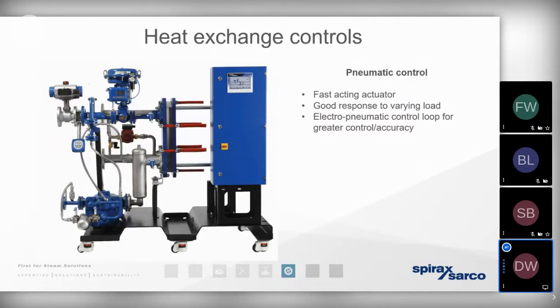So, for example, we can have a PLC panel, as you can see here, the heat exchanger package that's demonstrated in the middle of the screen, the various control valves, isolating valves, flow meters, steam traps. We can have a fully packaged solution that's easy to install and maintain that can bring a lot of benefits compared to a traditional shell and tube heat exchanger.